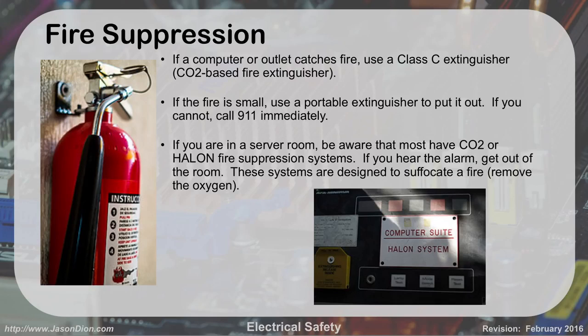The reason why is if we have a fire in a server room, we need to put that fire out really quick or it's going to spread to all the other critical assets. So all these systems have raised floors and drop ceilings, and they have all these systems set up so that it will completely fill the room very quickly with this CO2 or halon and suffocate the fire. So if you're working in there, get out, okay?